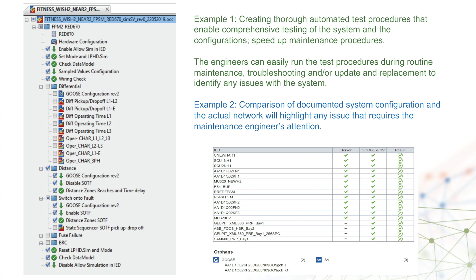This automated test procedure not only sets up the entire sample value stream, GOOSE configuration, and everything else, it also enables the simulation flag and test mode on the device being tested. Then it runs through its set of required tests, and at the end it disables the flags again. The engineer just needs to know how to work with this procedure, and beyond that it's all automated. Yes, it runs all the tests again, but that's probably far less time than running them individually and remembering every step to restore the system to how it was before maintenance. It's automated, runs smoothly, and takes maybe a couple of hours more, but it's far less intensive than doing it all manually.